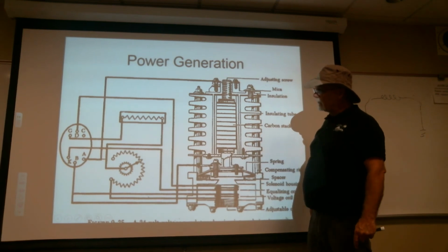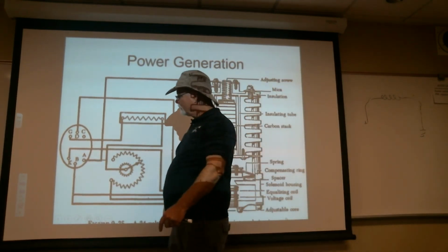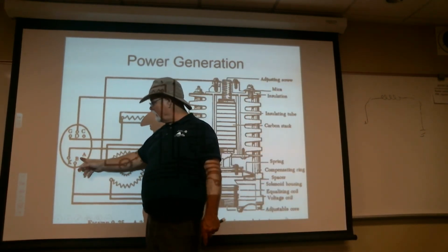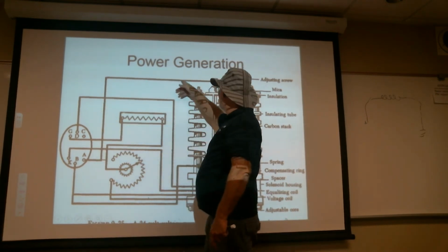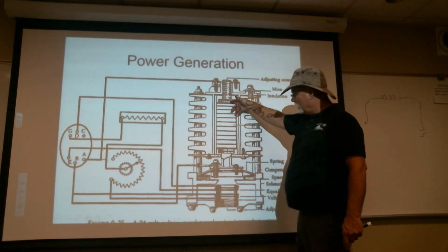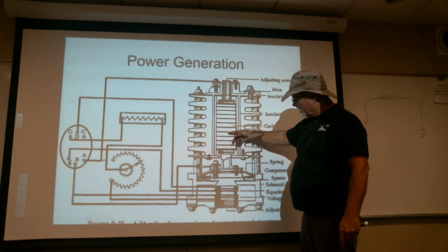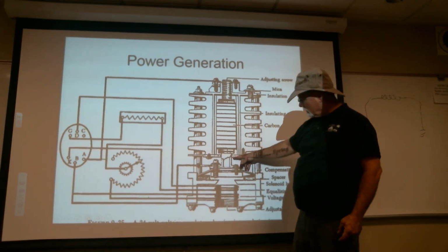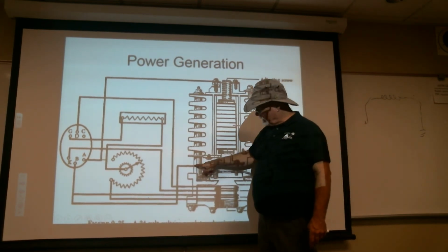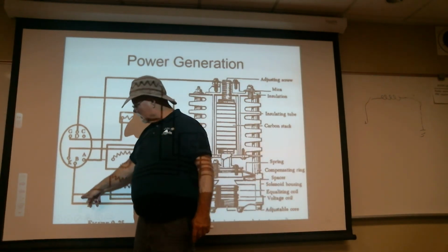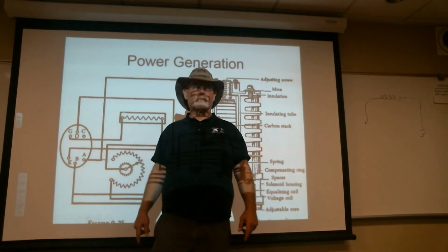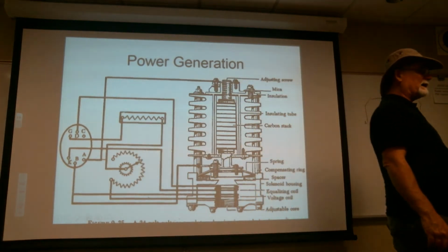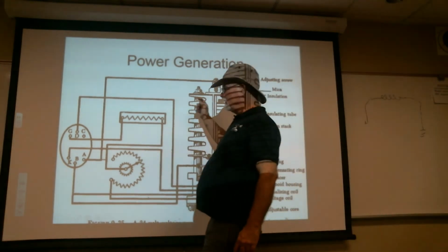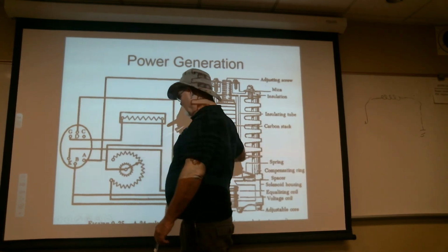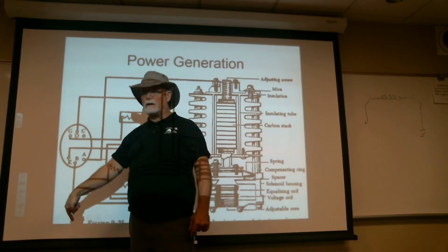I'm going to take my output to the field, on the negative side, and bring it in here, run it around like this, through the carbon pile, then to here - this is insulated - out this wire over to terminal B. Then I can connect that to ground. So power goes to the field, goes to A, goes there to B, goes to ground.